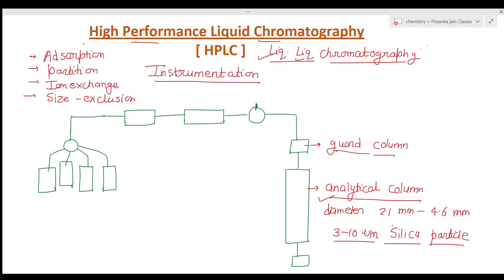Now, what is the use of the guard column and why are we using it? There are two problems in HPLC that can shorten the lifetime of the analytical column. First, the solute can bind to the stationary phase irreversibly, degrading the column's performance and decreasing the availability of the stationary phase. Second, particulate material injected with the sample can clog the analytical column.